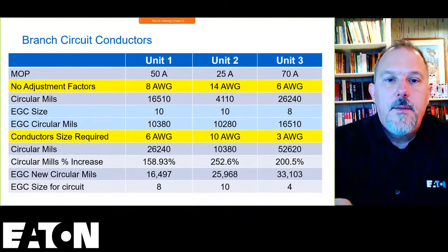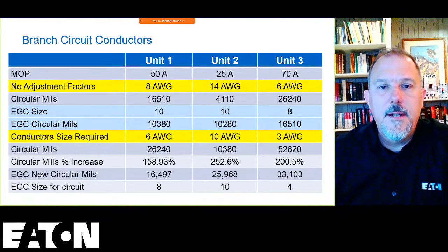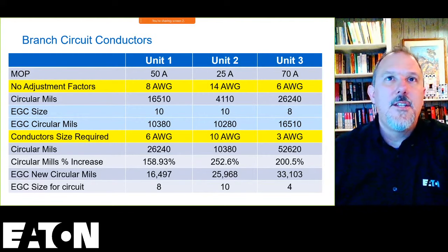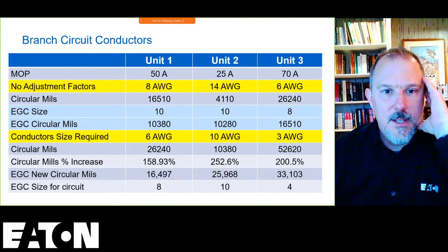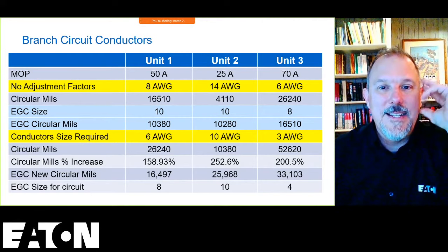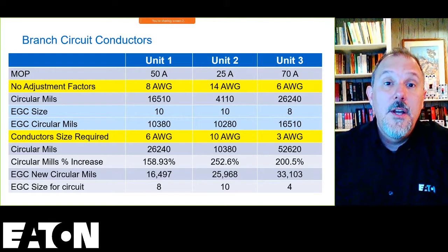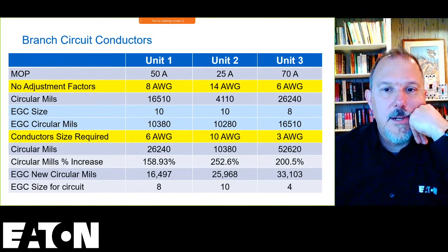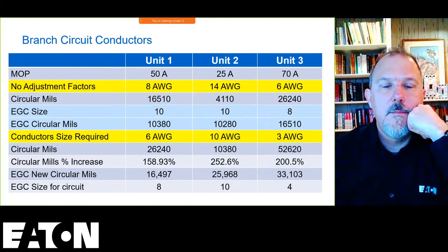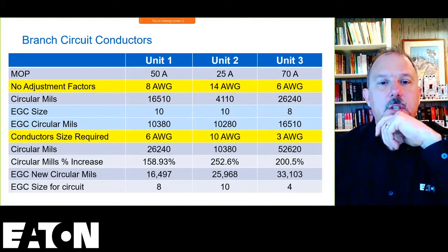is... I'm going to take a look at, hold on, I'm looking at my chat. I've been looking at YouTube chats and my Facebook chats, but I haven't been looking at the WebEx chat. Looks like they're talking about who's stocking what conductors, and that does play a really important role in what conductor you use. Must comply with requirements in 250.122, but it sounds like Tom said otherwise. No, it does have to comply with 250.122, Dawn. I agree with that. I may have misspoken there, but you do have to follow 250.122. Don't have to use the 60-degree ampacities for circuits 100 amps or less.